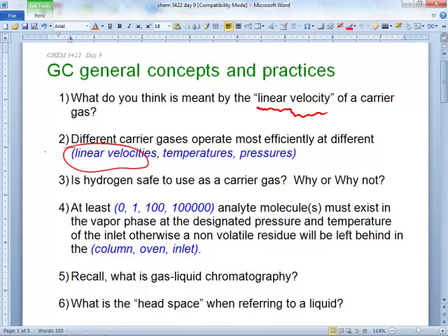So not only is it 5-9er gas, but I don't know if you look closely behind or beside the GC, there's this big cylinder, right? Stainless steel cylinder. It's about the thickness of my arm here, about that long too. And all the carrier gas flows through there. It's an absorbent to get rid of even more what? Gas. Oxygen. Just try to sweep it out of there.